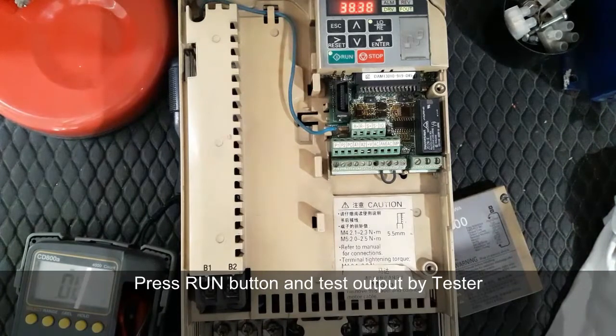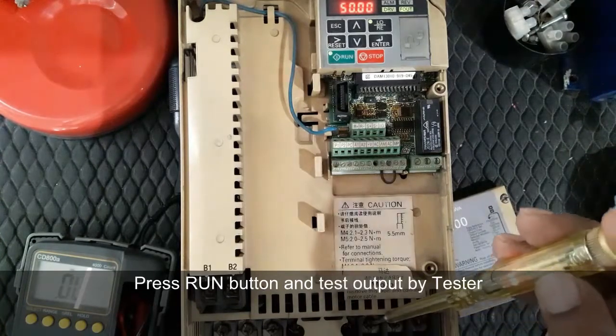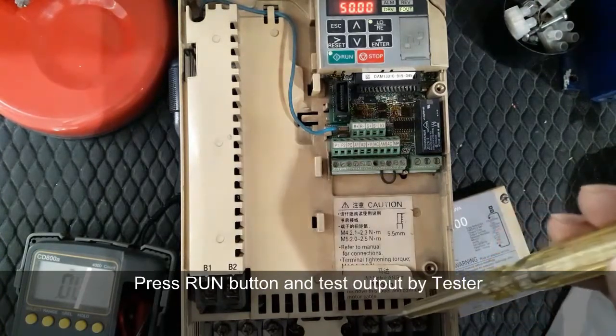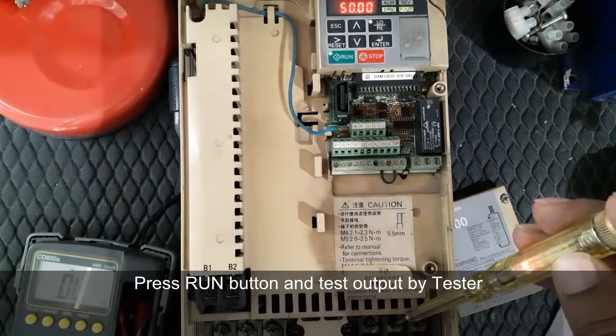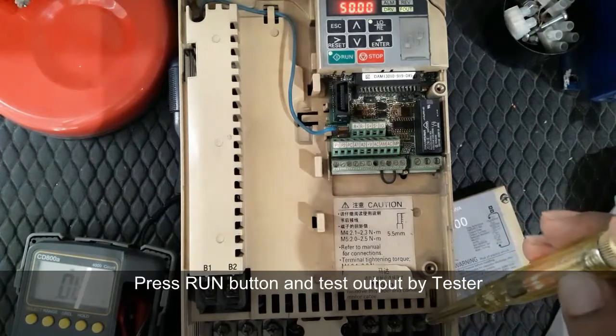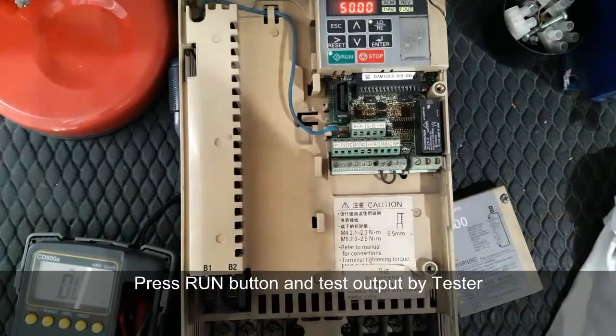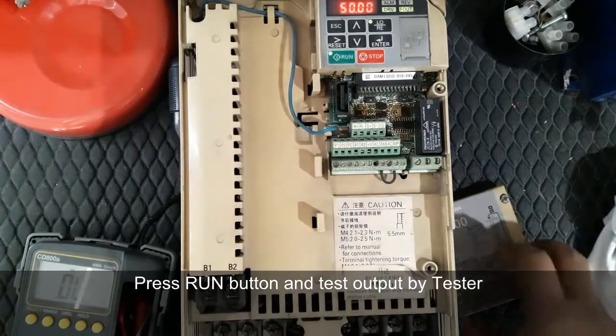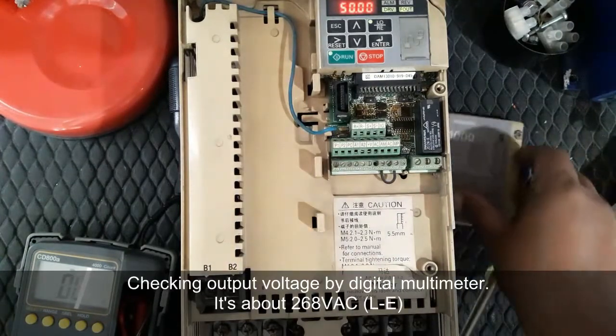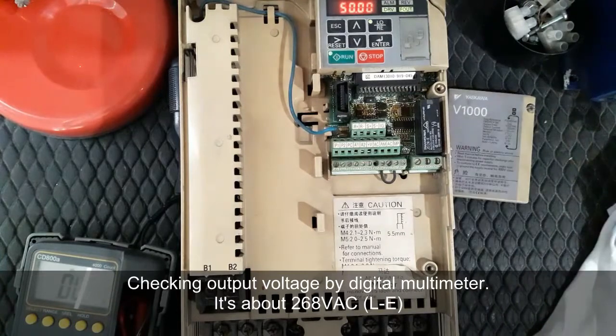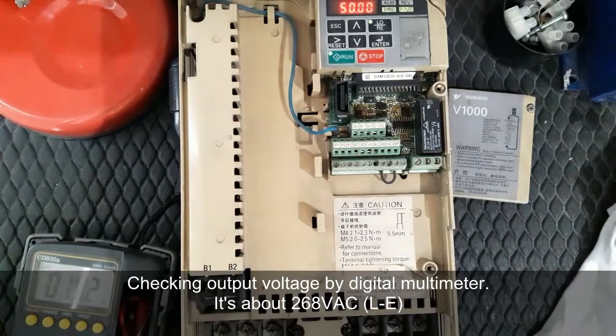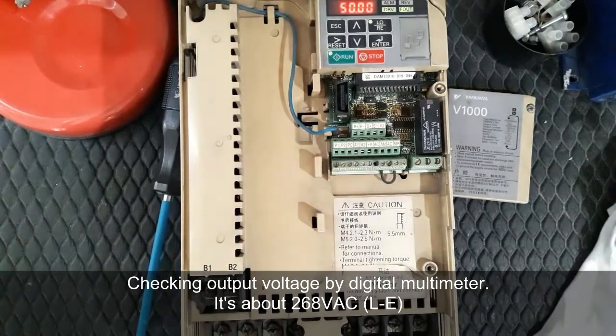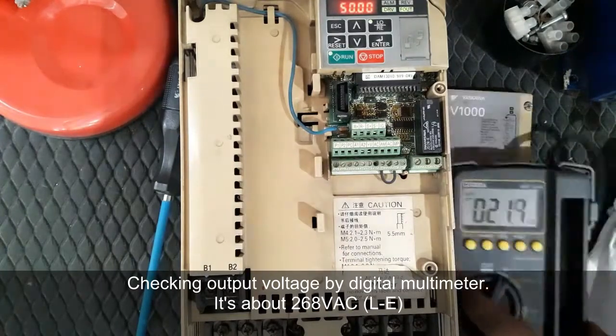The motor connection U, V, W means the inverter output. So here we are using a tester and it flashes on the 3 terminals U, V, W that we tested by tester. Also we want to check the output AC voltage with a digital multimeter. We will check the output AC voltage between the U, V, W terminals.